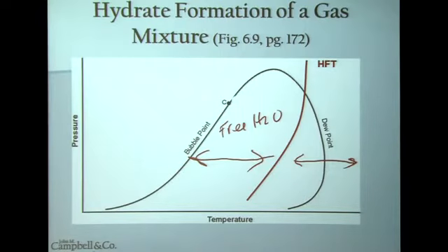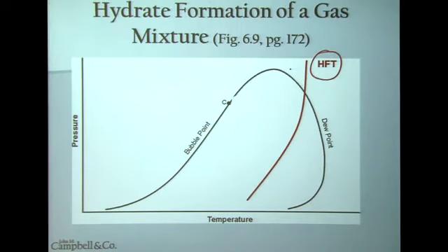So if you find yourself operating to the left of the hydrate formation temperature curve and you have free water in the system, you need to do something. One of the things that we discuss in this session is the calculation of the hydrate formation temperature.